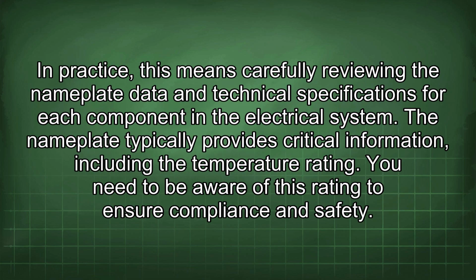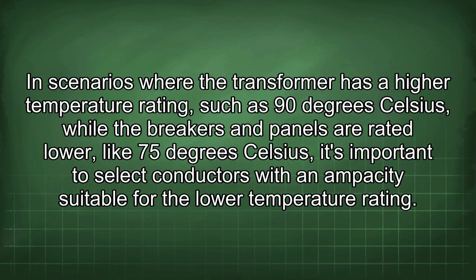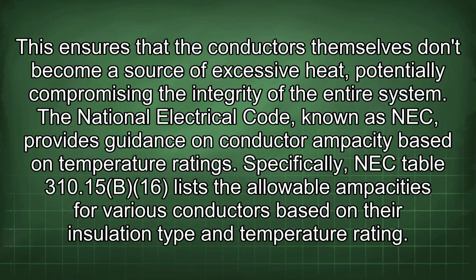In practice, this means carefully reviewing the nameplate data and technical specifications for each component in the electrical system. The nameplate typically provides critical information, including the temperature rating. You need to be aware of this rating to ensure compliance and safety. In scenarios where the transformer has a high temperature rating, such as 90 degrees Celsius, while the breakers and panels are rated lower, like 75 degrees Celsius, it's important to select conductors with an ampacity suitable for the lower temperature rating. This ensures that the conductors themselves don't become a source of excessive heat, potentially compromising the integrity of the entire system.